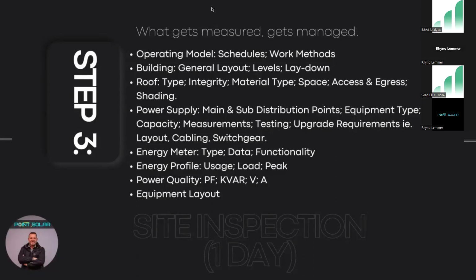When we talk about an energy profile, it concerns not only your usage but more specifically your peak demand and your average load. Your monthly statement might tell you you're consuming, say, X amount of kilowatts, but your actual peak demand could be a factor much higher than your average load. So you might be developing a system in the 100 kilowatt range, but your peak demand might be 300 kilowatts, requiring three times the inverter capacity.